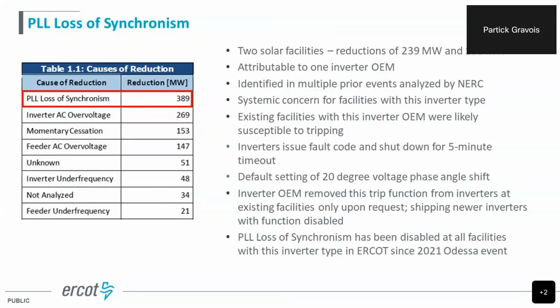So this occurs when there is a voltage phase shift greater than 20 degrees. We were able to talk with the OEM and discover that this function is not really necessary for equipment protection, and it really wasn't needed for the transmission level system. So this was one that we were able to fix relatively easily. The OEM said that they could disable this function upon request from the generator owners. And they are shipping out their new inverters with this function disabled.